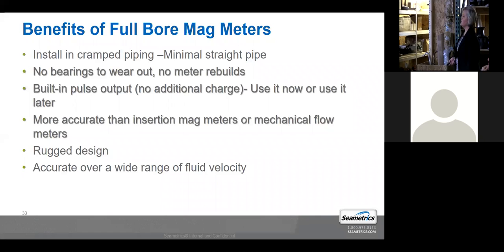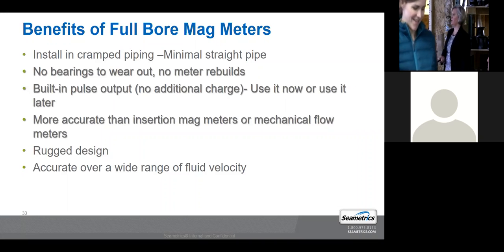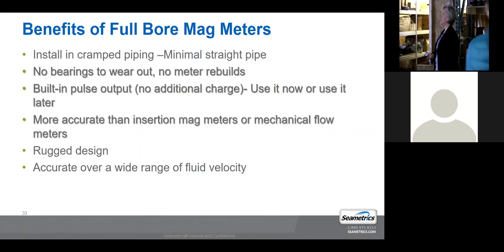The main benefits of full bore mag meters are they install in cramped piping, very tight spaces, with minimal straight run. You don't have any bearing assemblies, no parts in them to wear out. You know they're going to maintain their accuracy when you put them in because there's nothing to wear out in them. Built-in pulse output at no additional charge. Our pulse output and our Modbus output have been tested with a number of remote telemetry companies, and I'll touch on that in a minute.